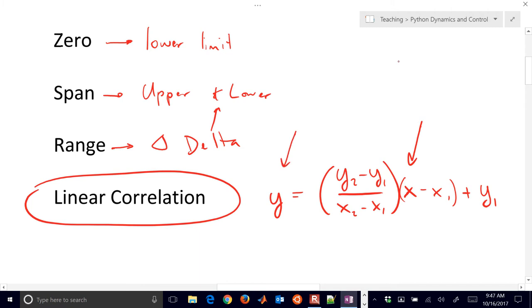And a lot of times this input is going to be a milliamp, 4 to 20 milliamp signal. Or it can also be something like a pressure as well. So you could have a sensor that gives you a 3 to 15 psig. Maybe for a pneumatic sensor. So you can have either one of these. These are common. You could also have 0 to 10 volts DC, for example.